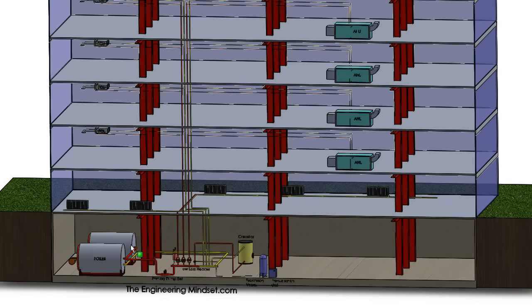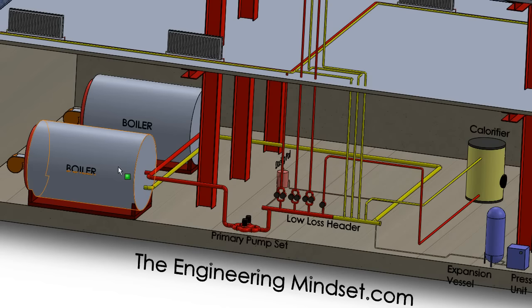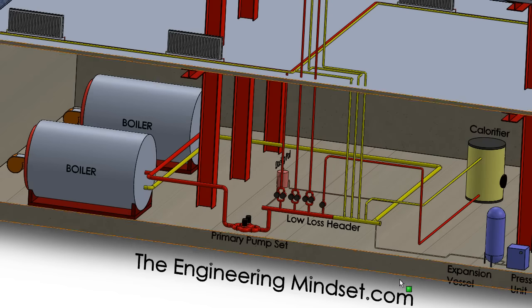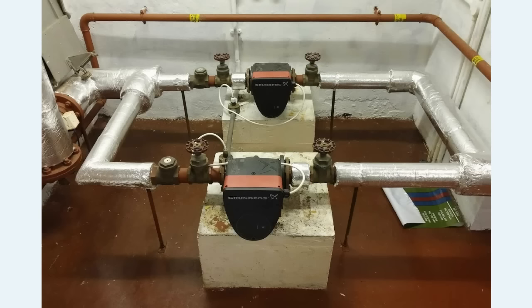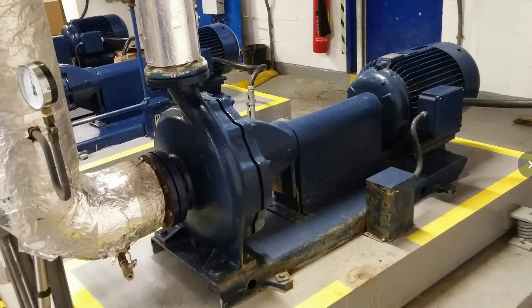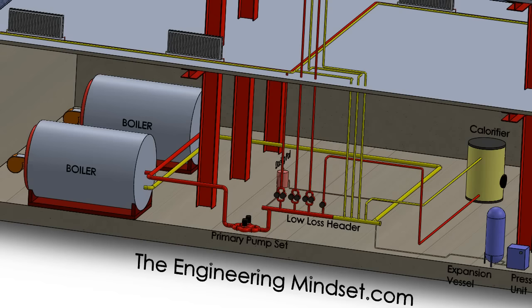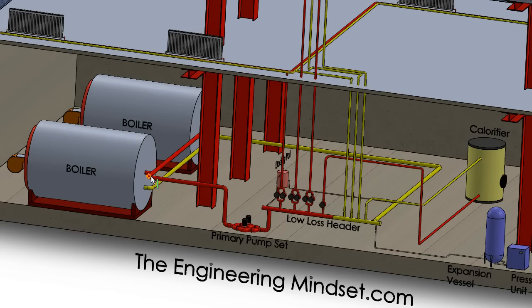So these boilers are the heat source for the heating system, and that heat is then pushed into the hot water of the heating system. One of the terms you'll come across in these sorts of systems is the terms primary and secondary circuits. As you can see here we've got the primary pump set — these two pumps here, which in the real world might look something a bit like this. These primary pumps will push the water around the system — around the primary side. That hot water leaves the boiler, enters into this pipe back here, is sucked by the pump and then pushed out into the low loss header, which we'll have a look at shortly.